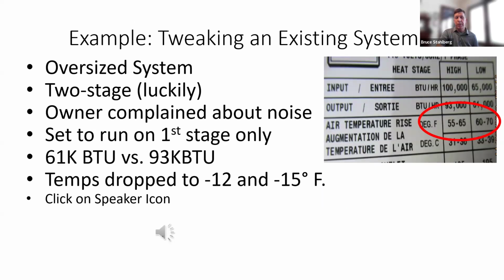This is another example. I went out to a home to check the water heater, looked at the furnace. It was a very large furnace at 100,000 BTUs. Owner complained about it being loud, and I set it to run on first stage only. So we went from 93,000 BTUs down to 61,000. We had temperatures that dropped down to 12 below and 15 below. And I talked to the owner, and he's like, it's just beautiful. It heats perfectly. It's not so loud. It doesn't wake us up. So it was a very easy tweak without replacing the furnace. He thought that they had many repairs over the 15 years, and he thought that might be why.